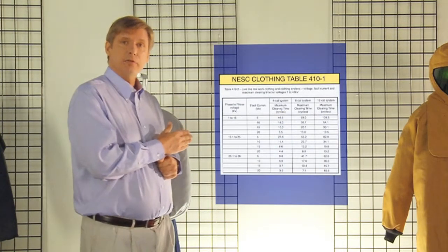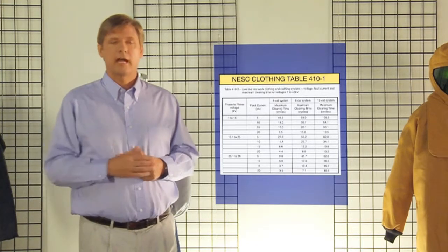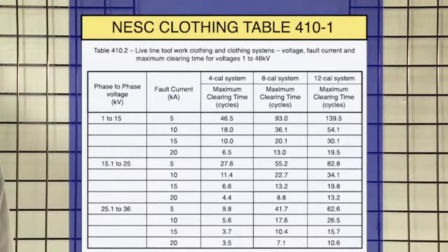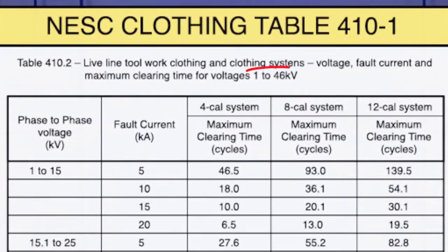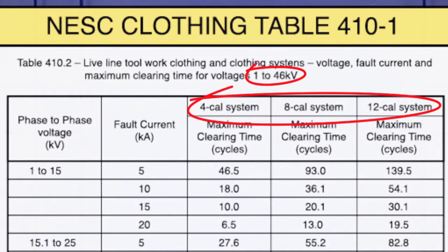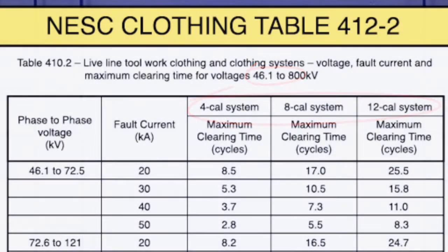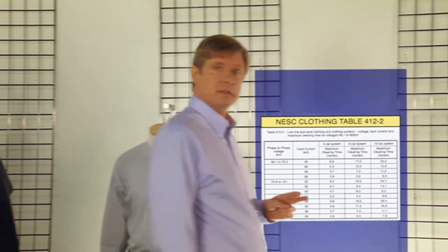The NESC tables are based on the voltage, fault current, and clearing times for various tasks. There are 2 tables. Table 410-1 for voltages 1 through 46 kilovolts. This outlines the FR clothing requirements with arc ratings of either 4, 8, or 12 calories per square centimeter. Table 412-2 for voltages 46.1 to 800 kilovolts. Again, based on fault current and clearing times, it outlines FR clothing requirements for 4, 8, or 12 calories per square centimeter. There are 2 exceptions to this table.